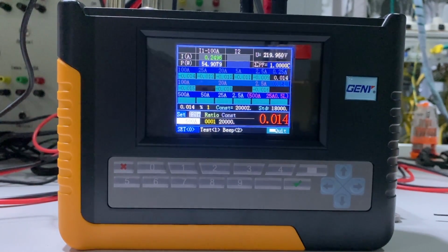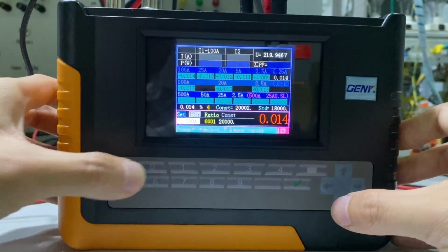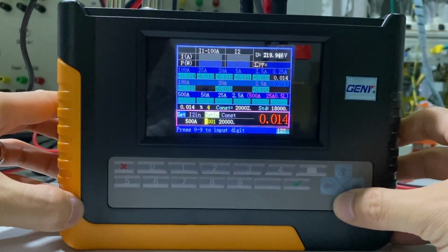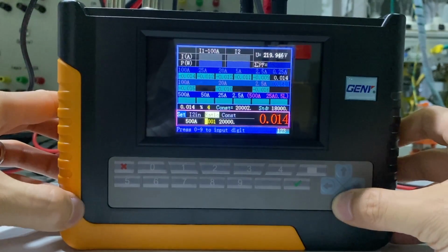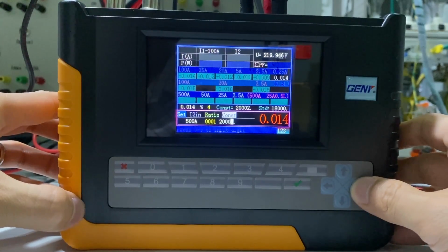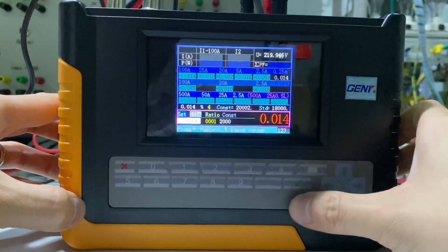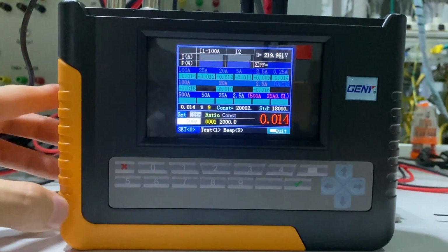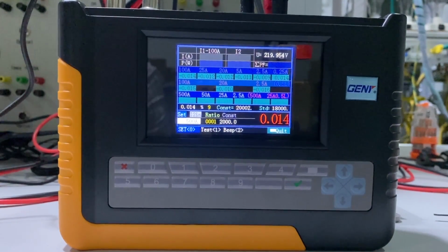Now we can move to the last calibration point. The last calibration point is 2.5 ampere, power factor 0.5 L. First lower the current. Stop the current. Then change the constant to 2000. The reference constant is set back to 2000. OK. Power source injects 2.5 ampere, power factor 0.5 L.